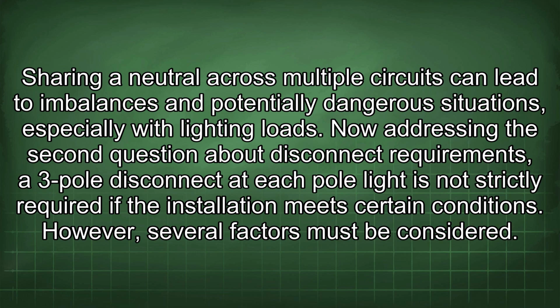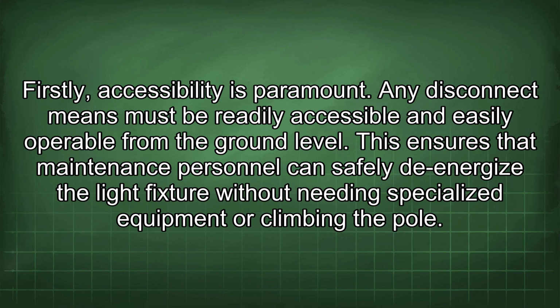Now addressing the second question about disconnect requirements, a 3-pole disconnect at each pole light is not strictly required if the installation meets certain conditions. However, several factors must be considered. Firstly, accessibility is paramount. Any disconnect means must be readily accessible and easily operable from the ground level. This ensures that maintenance personnel can safely de-energize the light fixture without needing specialized equipment or climbing the pole.